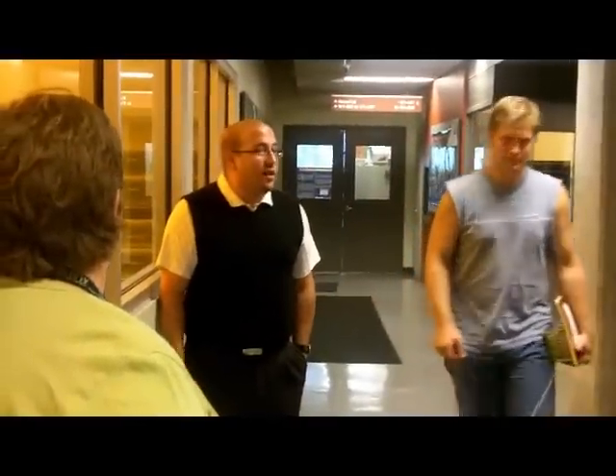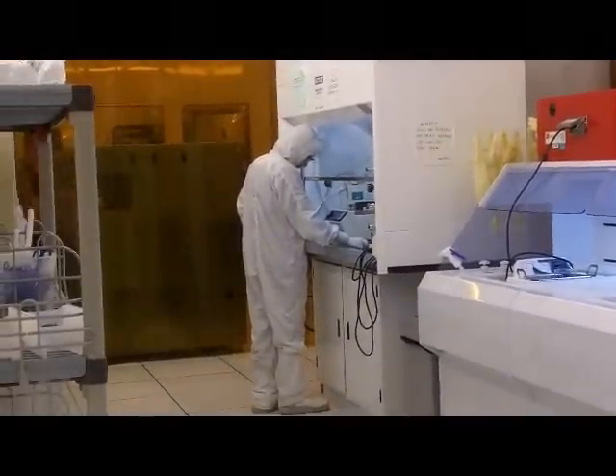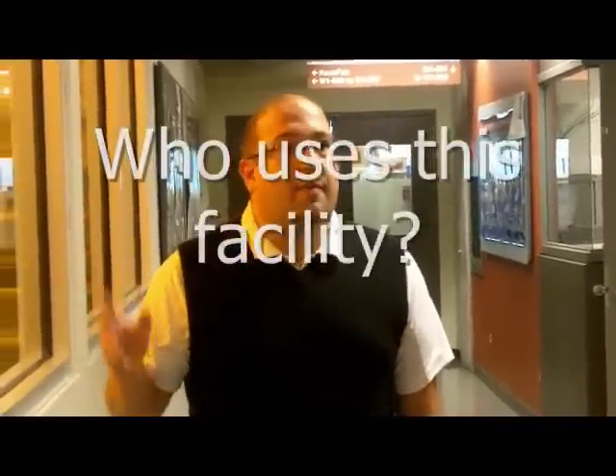The room inside here was designed to be a Class 1000 cleanroom, which is the same degree of cleanliness as an operating room. We actually run 100 times cleaner than that based on our protocols. What we mean by that is there are fewer than 10 particles within a cubic foot of air at any given time.